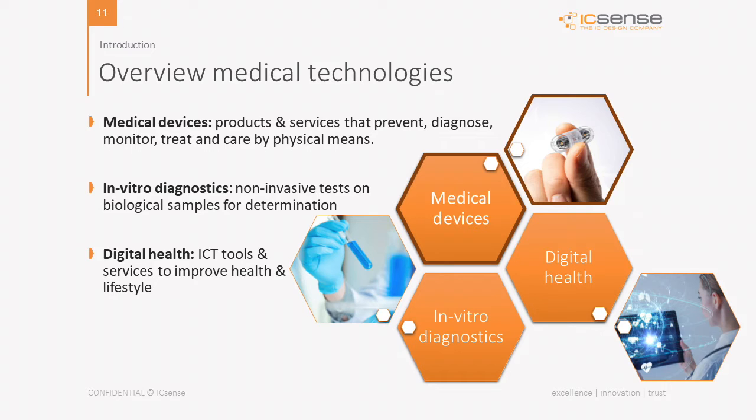The first one is the medical devices, that are products, services, or solutions that prevent, diagnose, monitor, treat, and care by physical means. It can be in or on the body, but with no pharmaceutical, immunological, or metabolic means. The second category that can be identified is the in vitro diagnostics, also called IVDs. These non-invasive tests are used on biological samples like blood, urine, tissues, and are used to determine the status of a person's health. And then the third category is what we call digital health.